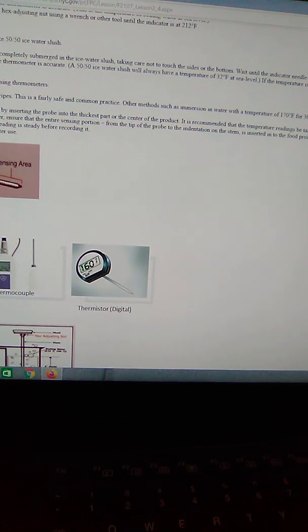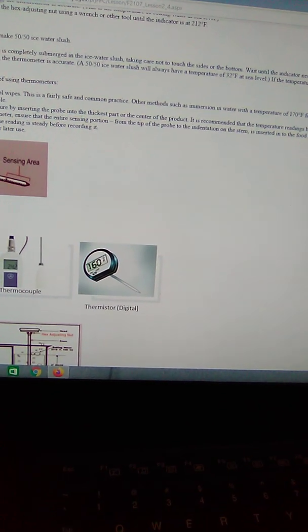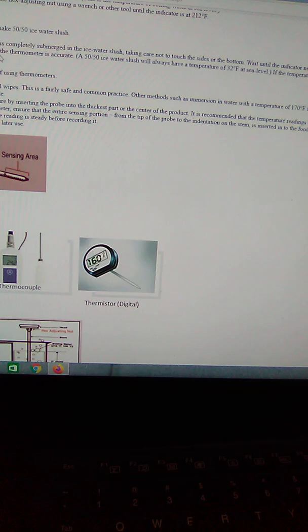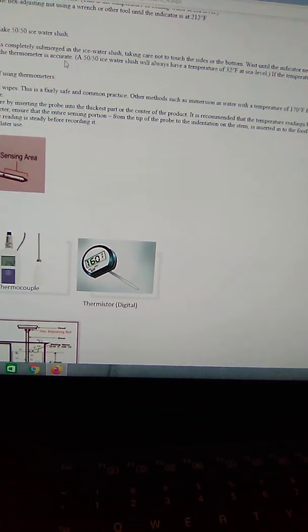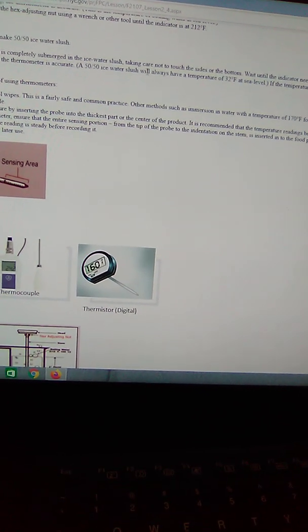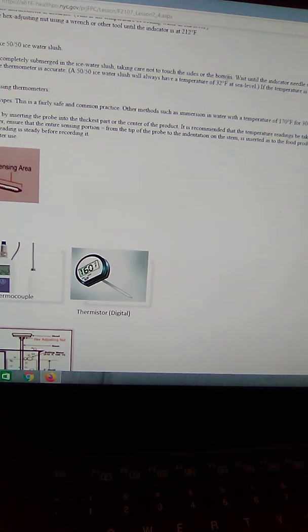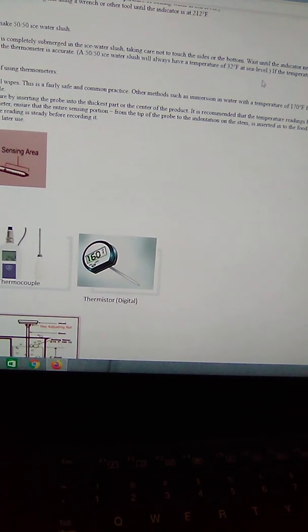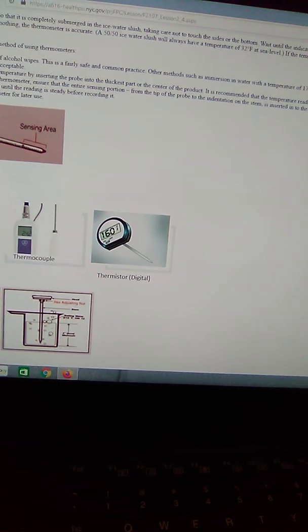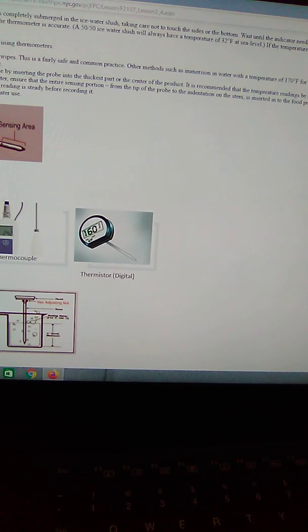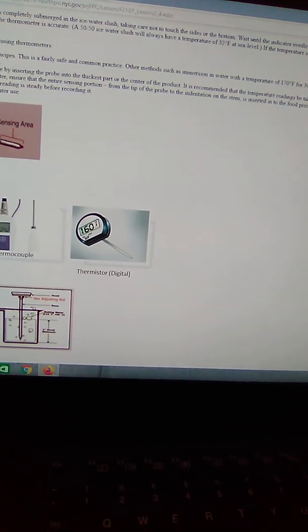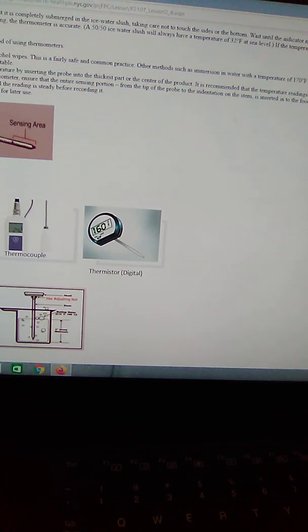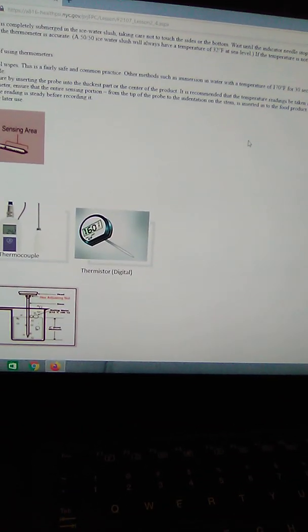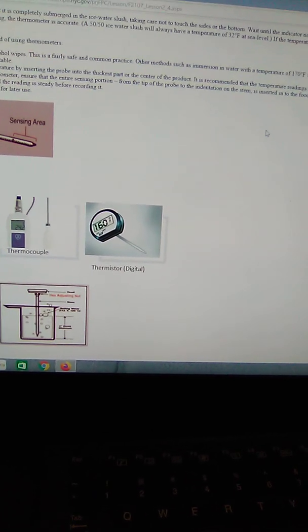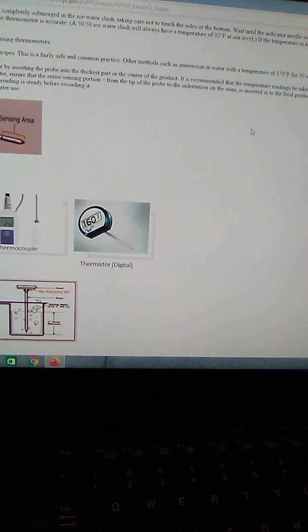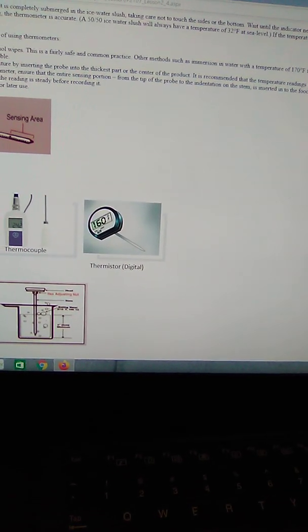Okay? If the temperature is, I repeat, is 32 degrees Fahrenheit, do nothing. The thermometer is accurate. A 50-50 ice water slush will always have a temperature of 32 degrees Fahrenheit at sea level. If the temperature is not 32 degrees Fahrenheit, rotate the hex adjusting nut until the indicator needle is at 32 degrees Fahrenheit. So when you're doing the ice water test, you want to make sure you have a 32 degree Fahrenheit reading. If your thermometer is not reading 32 degrees Fahrenheit, you got to adjust it so that it does.